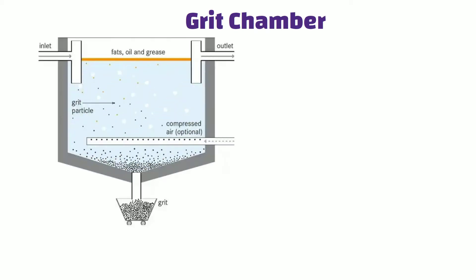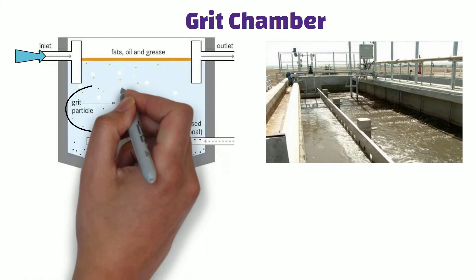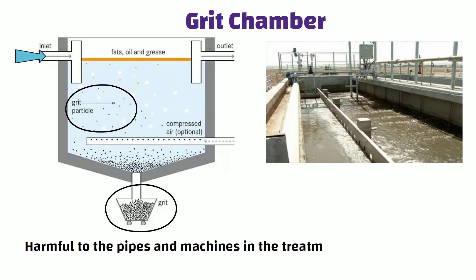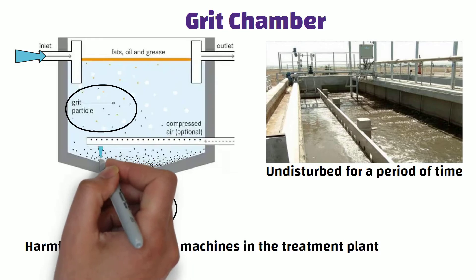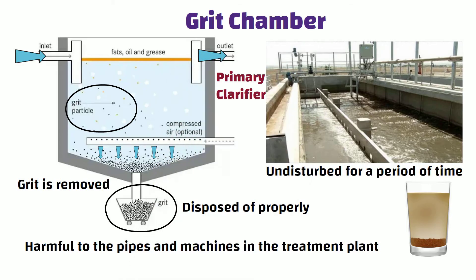Grit Chamber: from the bar screen chamber, the waste water enters the grit chamber through an inlet pipe or channel. This is where small bits of solid material — too small to be removed by the bar screen — are removed. These small bits, called grit, can be harmful to the pipes and machines in the treatment plant if not removed. In the grit chamber, the water is left undisturbed for a period of time, allowing the grit to settle to the bottom of the tank, similar to sand settling in a jar of water. The grit is then removed and disposed of properly, while the water at the top is sent to the primary clarifier for further cleaning.